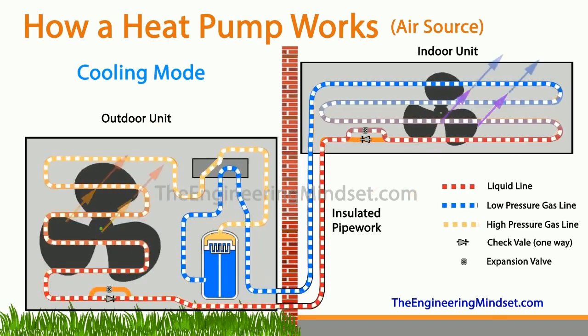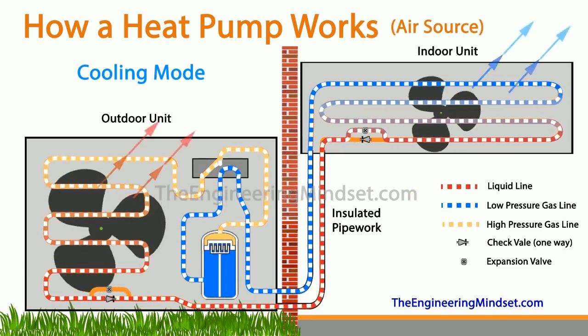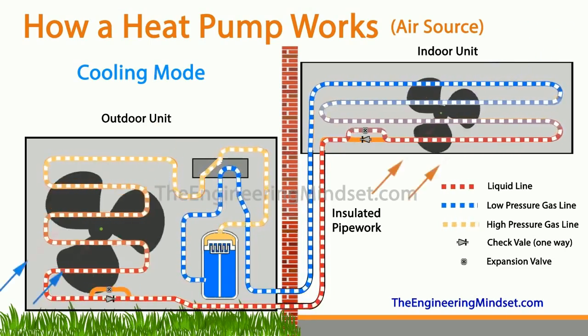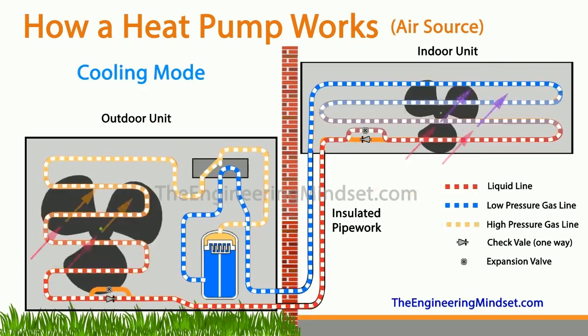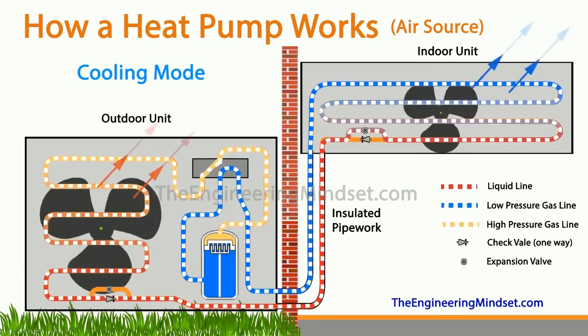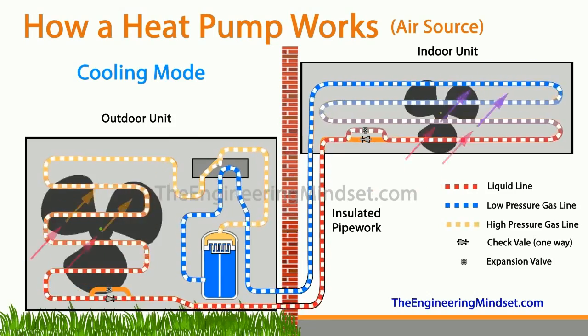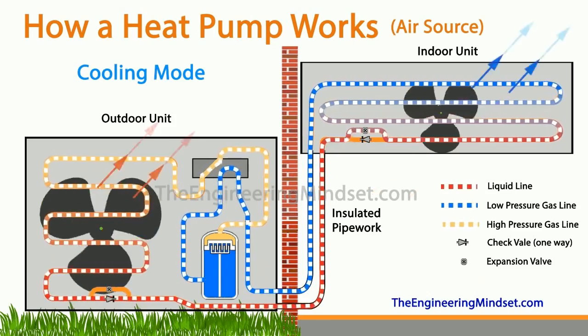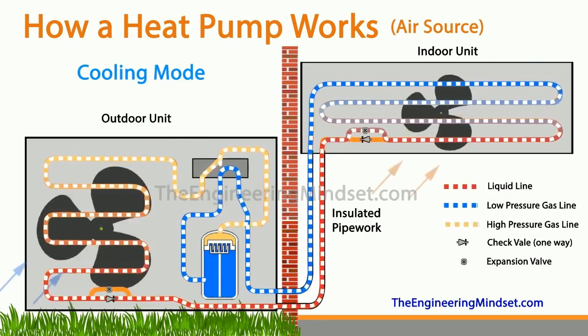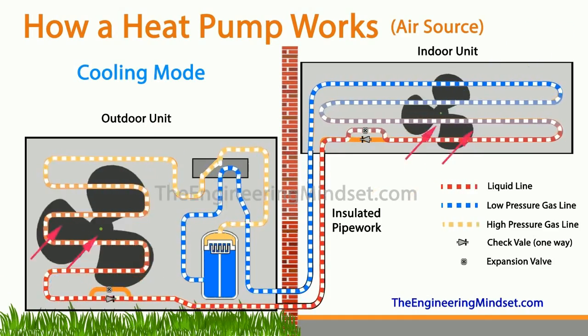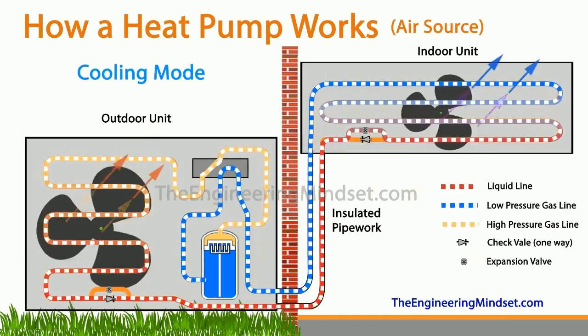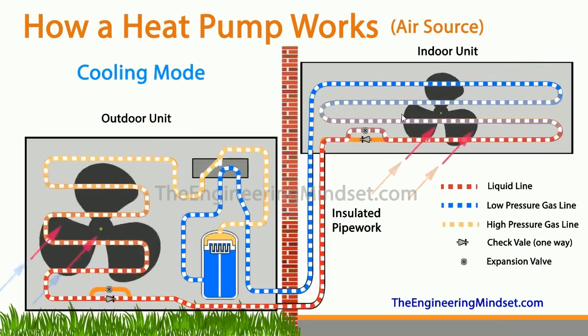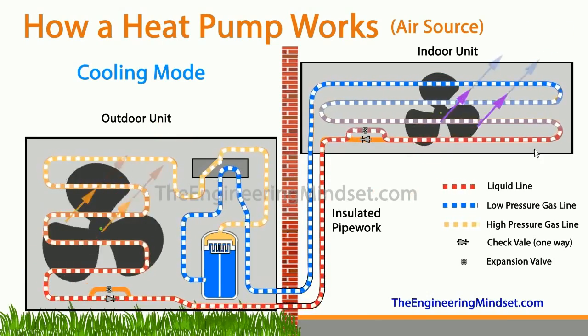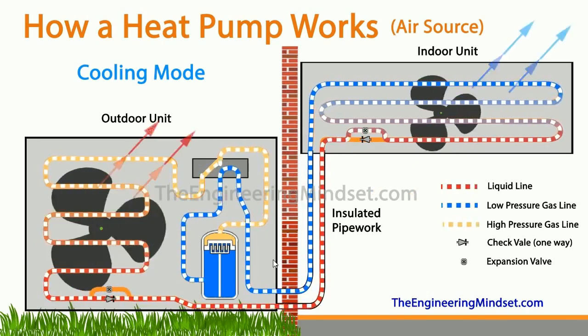So the refrigerant, when it enters into the indoor unit, which is acting as an evaporator, it enters there as a liquid vapor mixture, but the refrigerant has a very low boiling point, so the temperature of the inside air within the building is enough to actually boil this refrigerant and turn it into a saturated vapor, and that's still being pushed out by all the refrigerant that's being pumped behind it from the compressor.